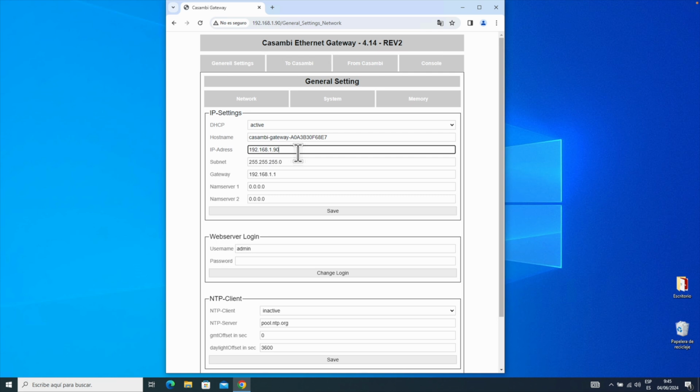Okay, so what IP address should we set it to? Well, we should set it to an IP address that allows us to read it from the Adquio controller, depending on which Adquio controller we are using. If, for example, it is a Pro or a Lite, we could set it to 172.20.20.x, because those are the IP addresses of its LAN ports. That would be the most correct and safest thing to do, that these Ethernet gateways would be on the LAN side of an Adquio Lite or an Adquio Pro controller.